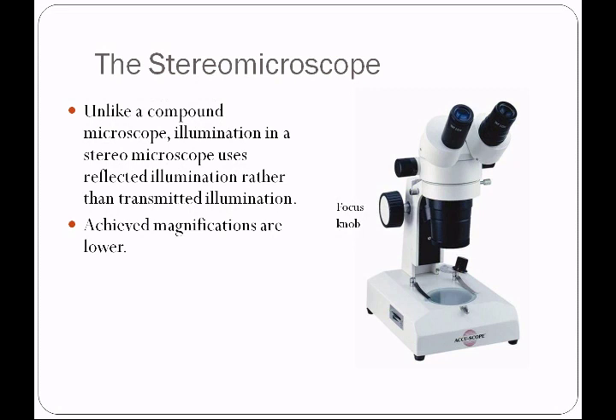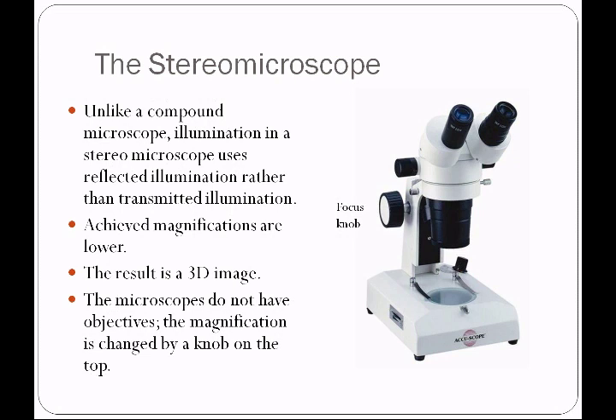The magnifications from a stereomicroscope will be lower than from a compound microscope — about 45x on these. The result is a three-dimensional image. The microscopes don't have objectives; magnification is changed by a knob on the top. There's also a focus knob on the side. There are two light settings: incident light that comes down from the top and bounces off the specimen, and light that comes through the bottom.